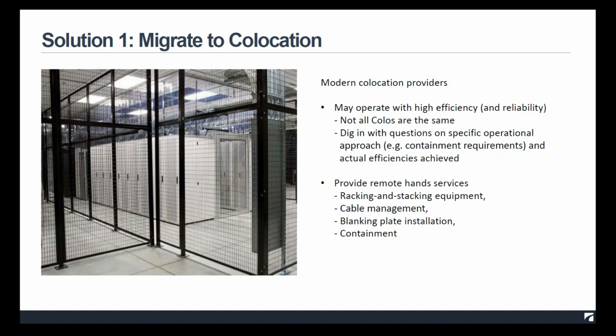As an example, one of the things that we do is we actually require our customers to use containment. So Steve talked earlier about the benefits of hot aisle, cold aisle containment. We've required hot aisle containment as part of our approach since 2008. There's always going to be some benefit in doing containment, but there's a greater benefit if everyone and all cabinets within the data hall use containment. So if a co-location provider says, sure, you can do containment, that's not going to be as effective from an energy standpoint as, yes, you must do containment in that facility. And there's other approaches besides hot or cold aisle containment, but containment is certainly, I'd say, a best practice.